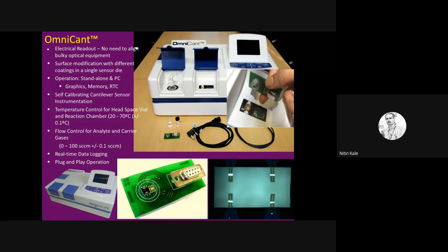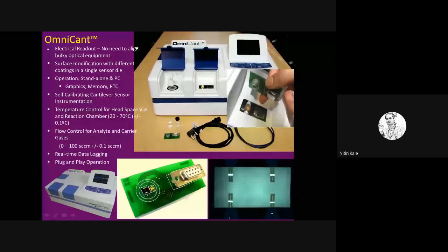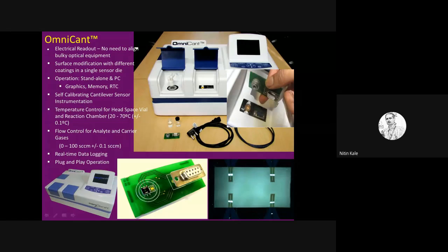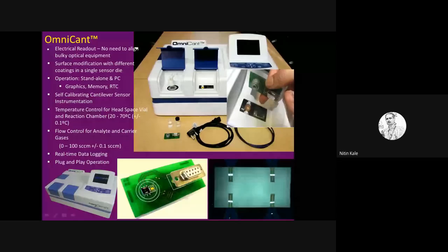And this is the electrical connection for the reaction chamber. We call this the flow cell, and this is the connector other part. The cantilever is present inside this. Okay. So when you fit this here, the gases that are coming from the flow path are going to interact with the microcantilever. This is how the PCB looks from another view. The flow cell is fitted here, and the connector is here, and this is the die.